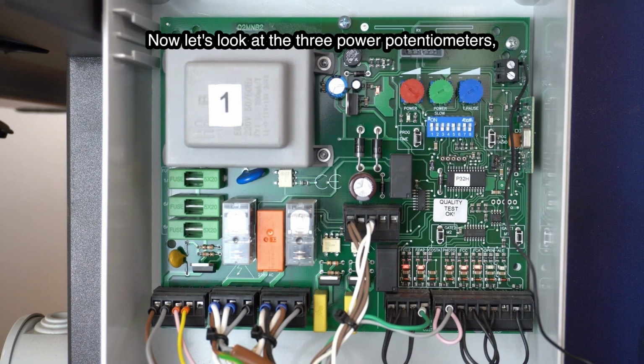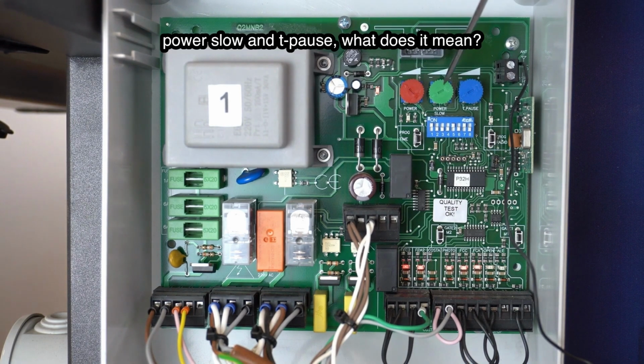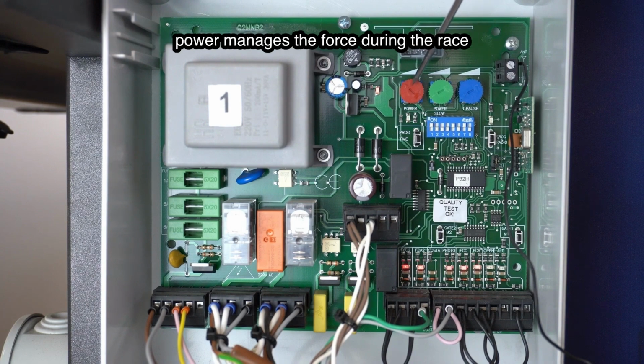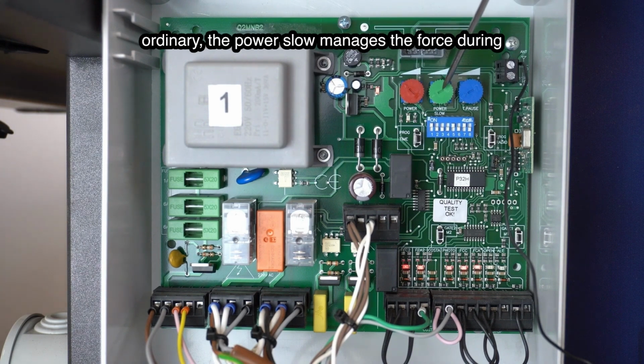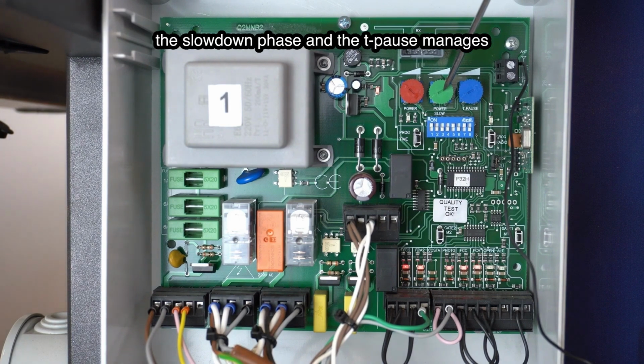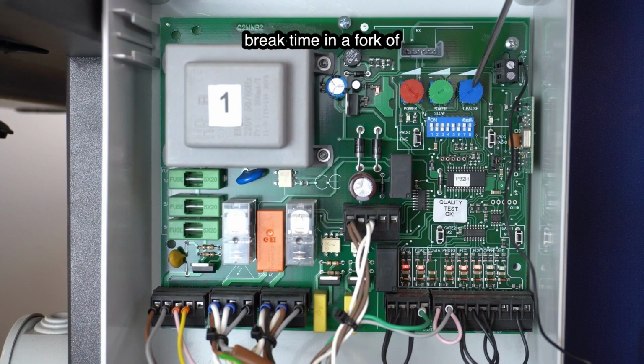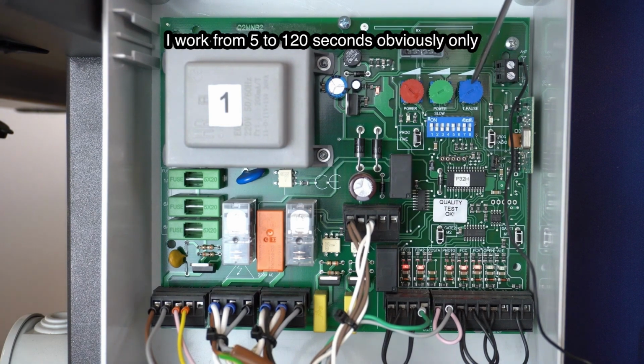Now let's look at the 3 power potentiometers, which are essential components: Power, Power slow and T-pause. What does it mean? Power manages the force during the run. The Power slow controls the force during the slowdown phase, and the T-pause manages the pause time in a range of about 5 to 120 seconds.